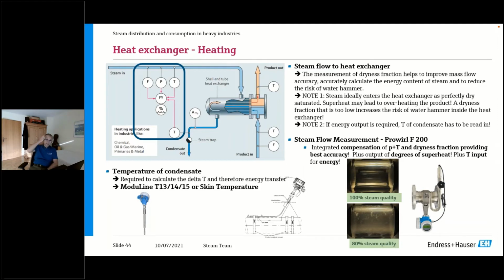I mean, it of course is important that you measure pressure and temperature because you may have superheated steam at this measuring point. Too much is no good. So if you're coming out of a PRV and that is working, then you may still have superheat at this point. Up to 15 degrees C of superheat is typically still okay because then you allow an extra size of your heat exchanger, but you must watch out that your product can abide 15 degrees C of superheat. This is also important.